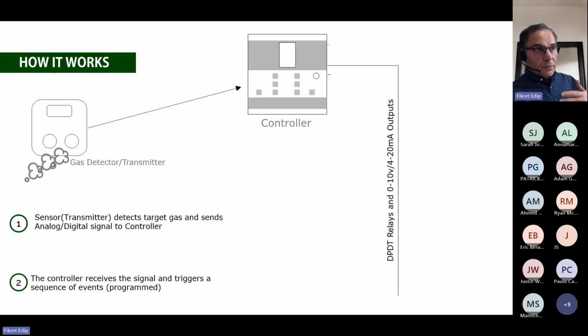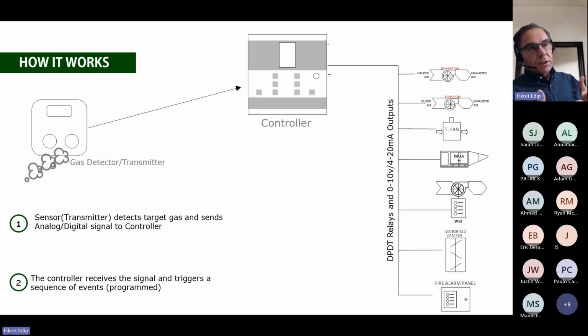So now the controller receives that signal. Depending on the model and the complexity of the controller, it has dry contact relays, or in some cases, it has 0 to 10 or 4 to 20 milliamp outputs. Once the controller receives that signal, and I'm a programmer sitting here programming this for a certain thing, I'm going to start exhaust fans, supply fans, transfer fans, makeup air units, and even VFDs and motorized dampers, etc., which you are very, very familiar with.